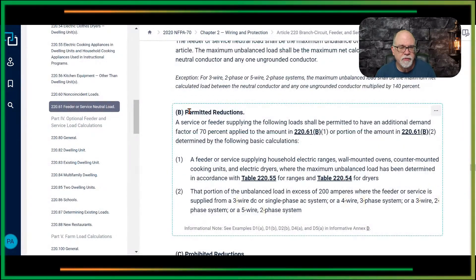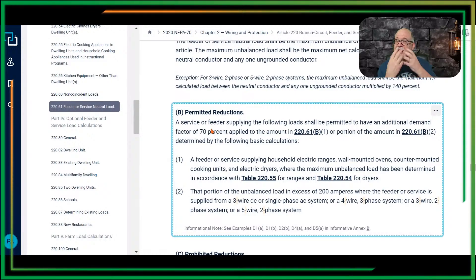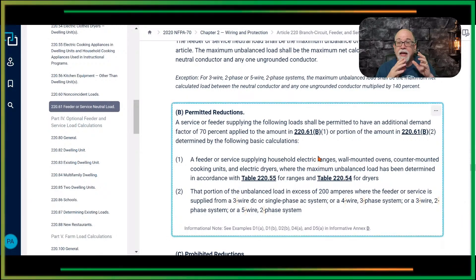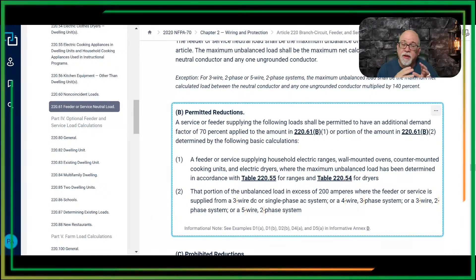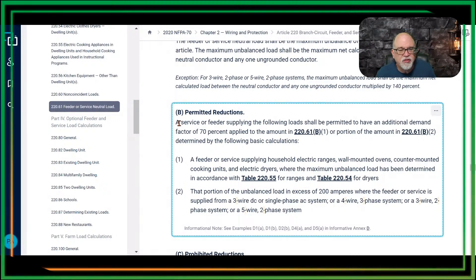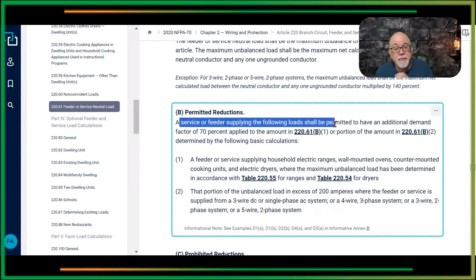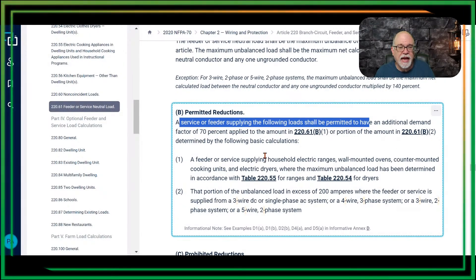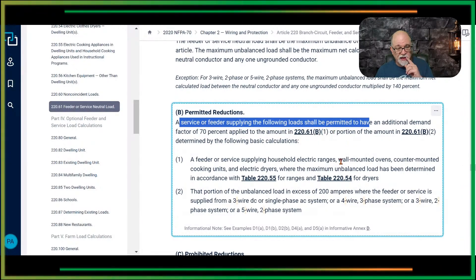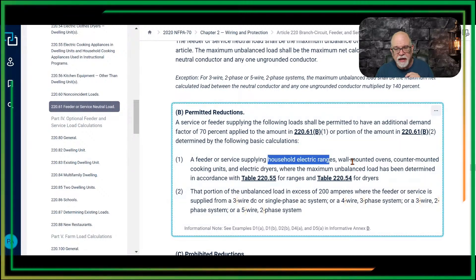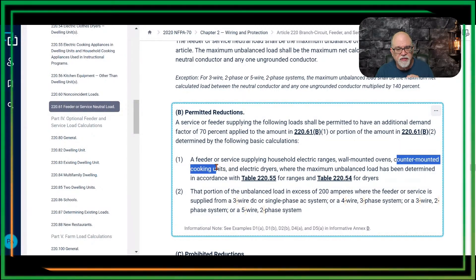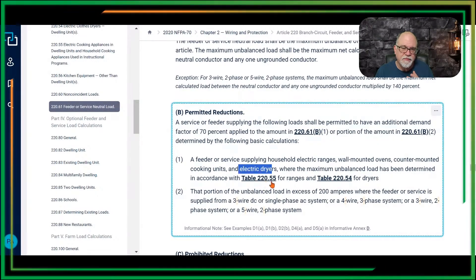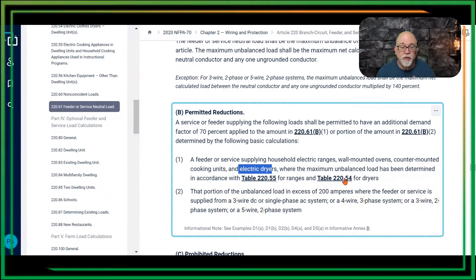Where does it say that? Right here — here's your permitted reduction. It's allowing you to take the amount you'd typically use to size the hot conductors and apply a demand factor of 70%. It says a service or feeder supplying the following loads shall be permitted to have an additional demand factor of 70% applied — see: household ranges, counter wall-mounted ovens, counter-mounted cooking units, and electric dryers. And it says where the maximum unbalanced demand has been determined in 220.55 (the range table) or 220.54 (the dryer table).